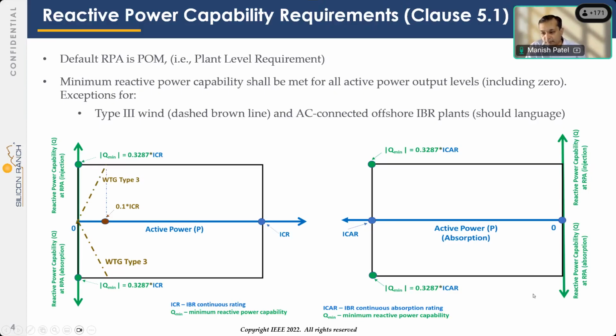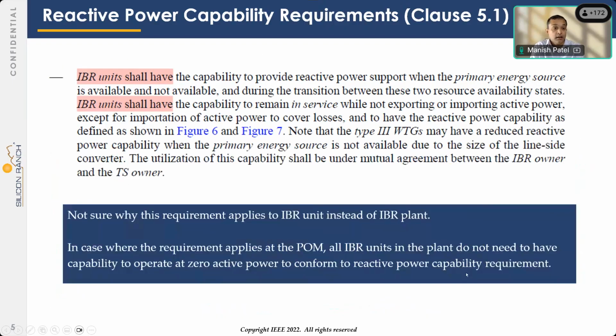The figure on the right is for plants that are able to absorb active power from the system, so battery energy storage, for example. In this case, ICAR is the IBR's continuous absorption rating in watts active power, and then reactive power capability is on the y-axis. Same as the other side of the slide here, 33% of ICAR, both absorbing and injecting. So that's what the standard requires.